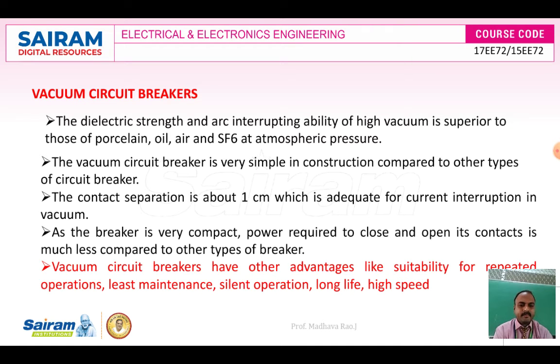That's why arc interruption is very easy in the vacuum circuit breaker, and the breaker is very compact. The power required to close and open the contacts is much less compared to other types of circuit breakers. So the size is very small, the contacts are very small, and the contact space between them is very small, and that's why the operation of this vacuum circuit breaker is very simple and very easy.